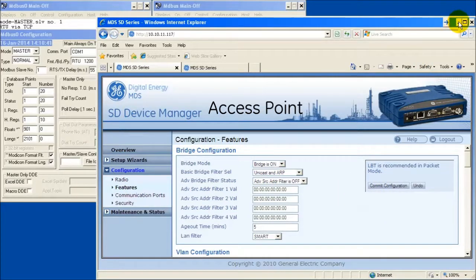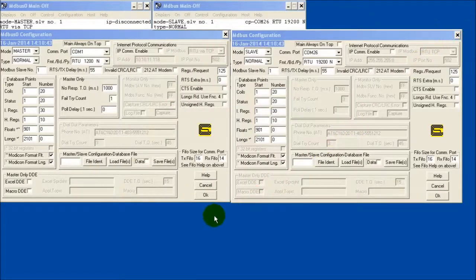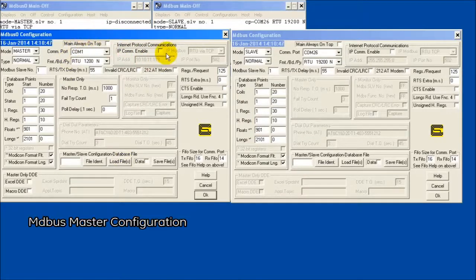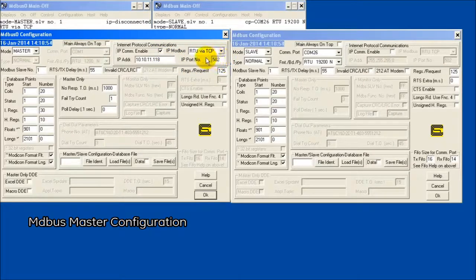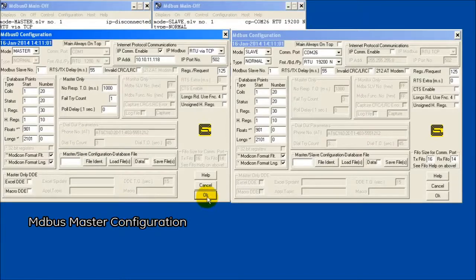Now I will configure a Modbus protocol polling tool, MDBus. The Modbus master I will set up to send RTU messages via TCP to the remote's IP address. I will send IP data on the remote's local IP port. The polling host, in this case a PC, is connected by Ethernet cable to the access point radio.